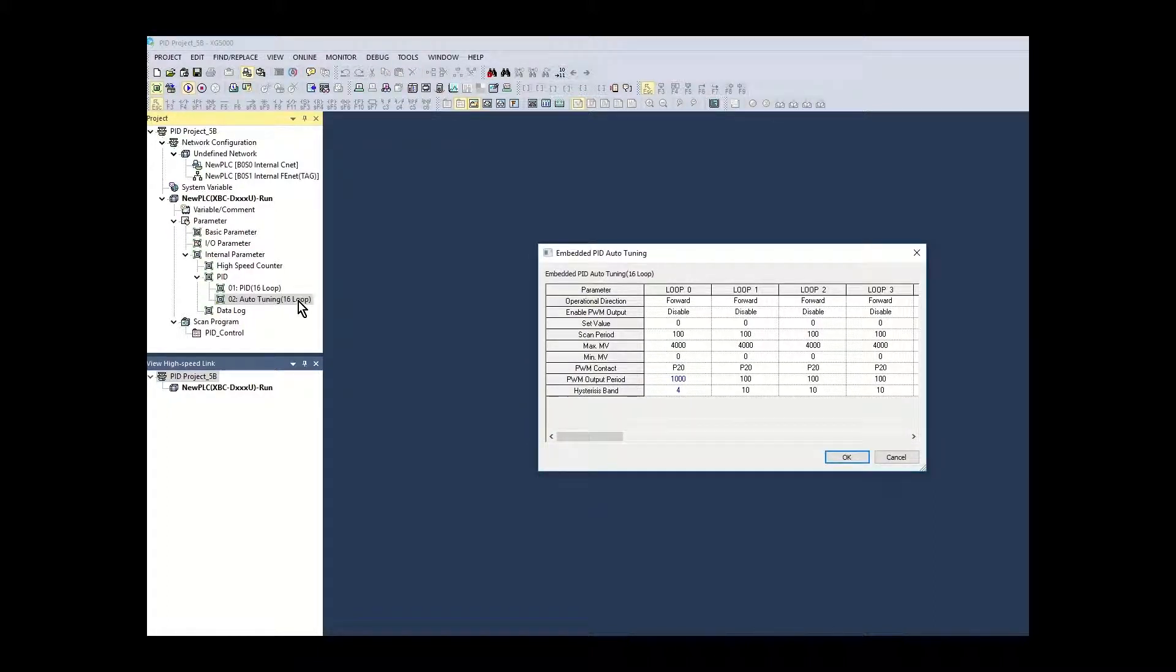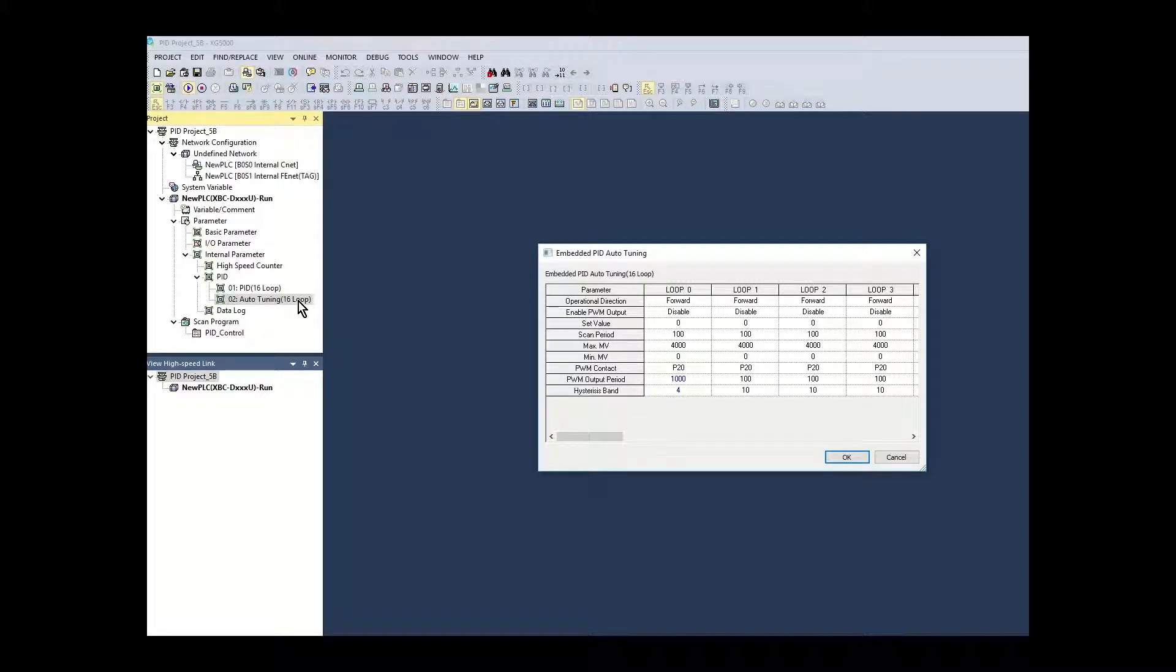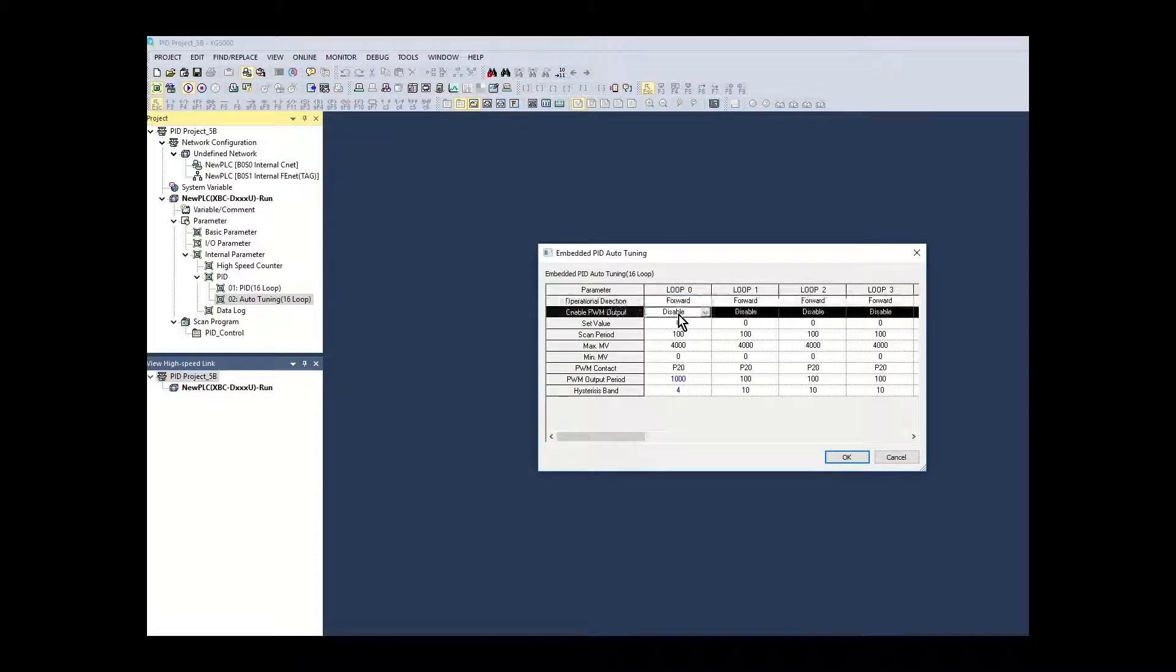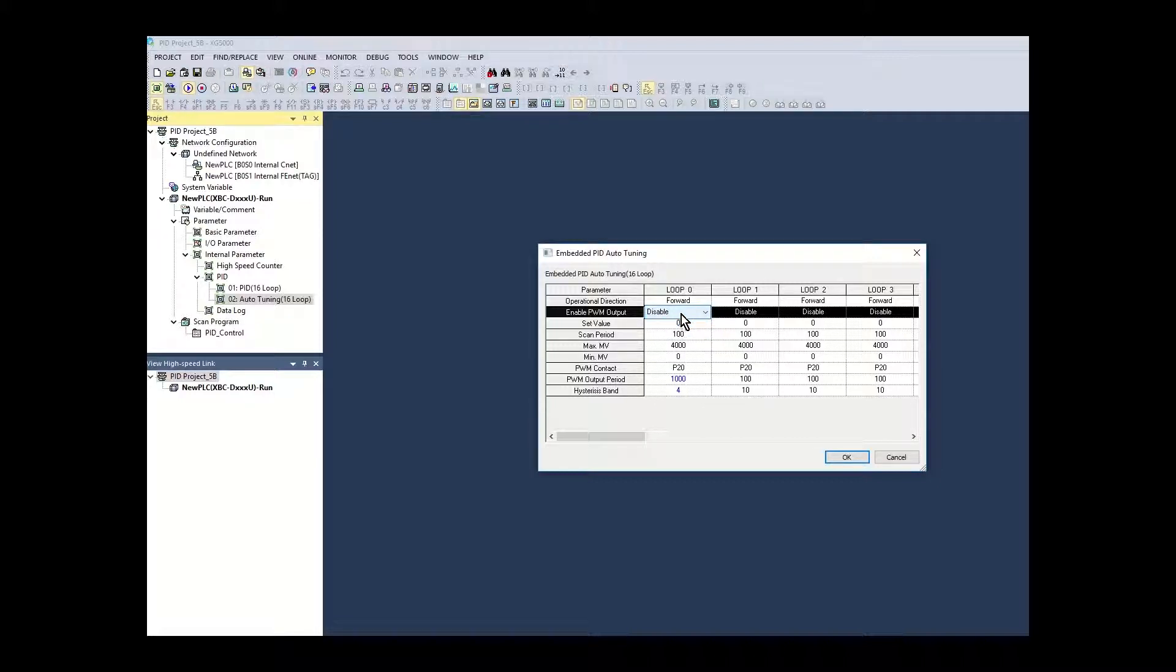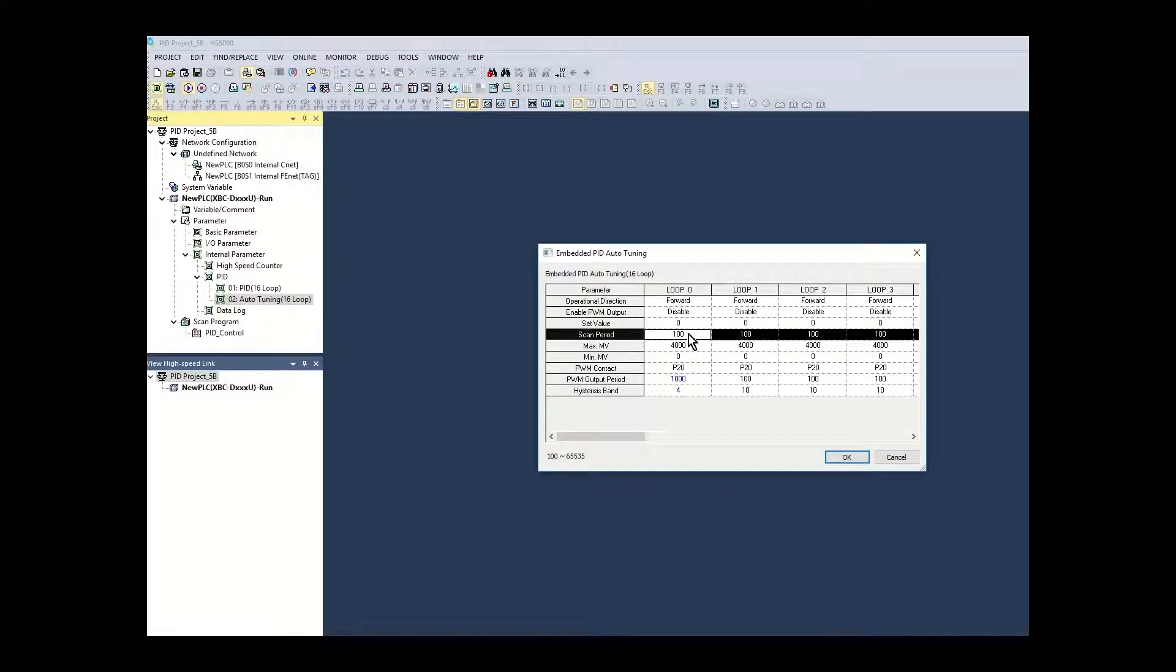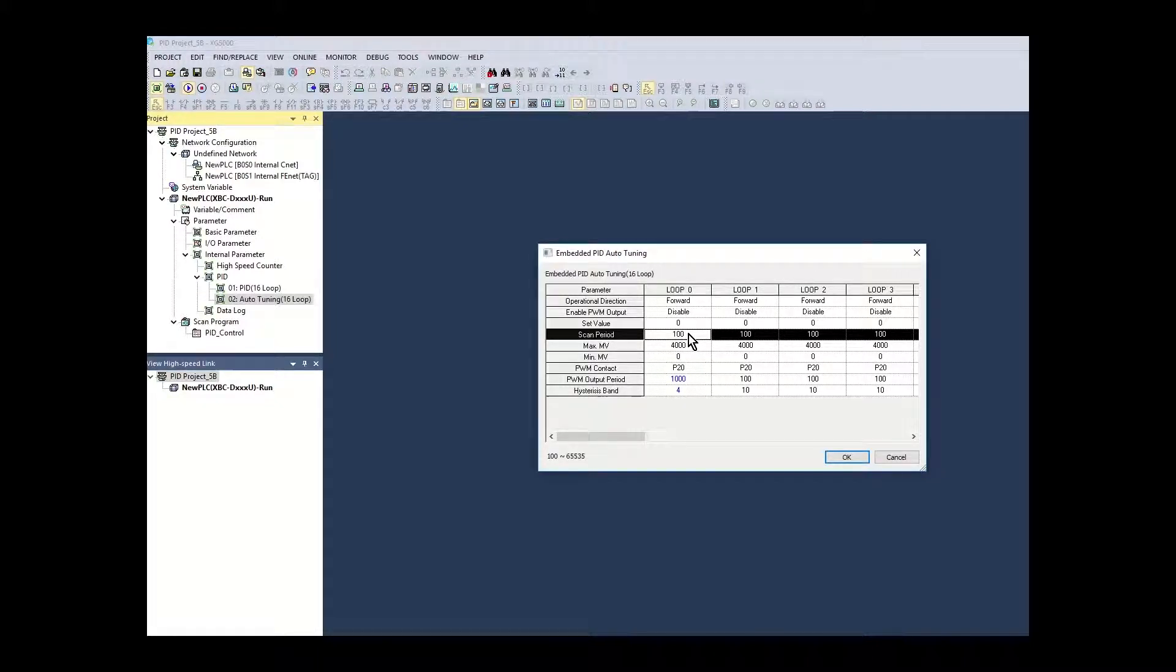These parameters are available for use in ladder logic when runtime changes are necessary. The operational loop direction is set for forward. Pulse width modulation is disabled as an analog output channel will be used for the MV output. The initial set point value is left at zero. This value will be set during autotuning. The scan period is set to 100. This is a 10 millisecond calculation cycle.